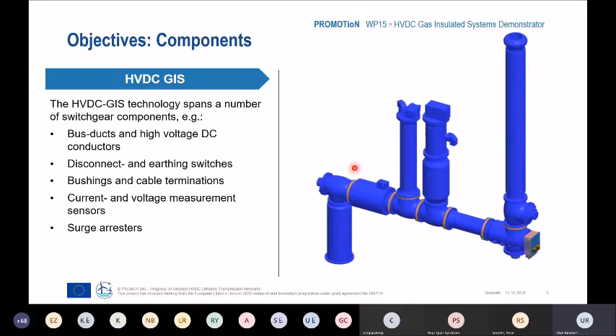The typical components you can see here on the right side, starting from the left, are the cable termination, so the connection from the GIS to a cable. That's very important for offshore applications. We have a lot of bus bars and connecting elements, a current transformer for current measurement, and a voltage measurement, typically for DC an RC divider, a surge arrestor, some switching elements, so a disconnector and an earthing switch, and a bushing, so the connection to other HVDC equipment.